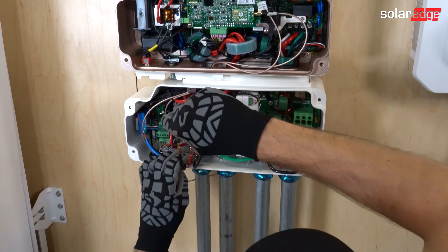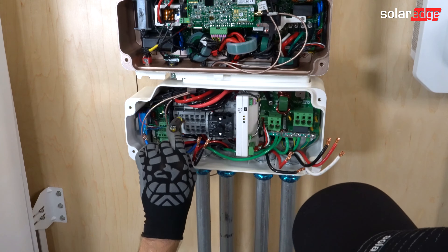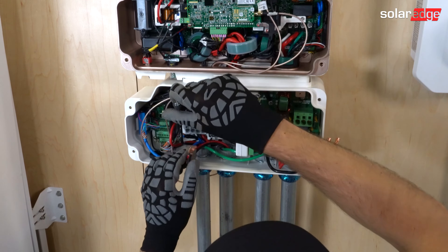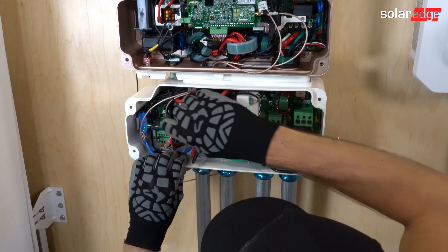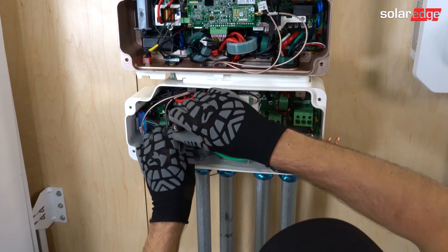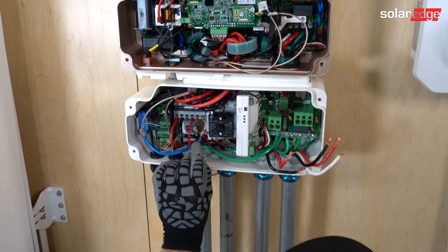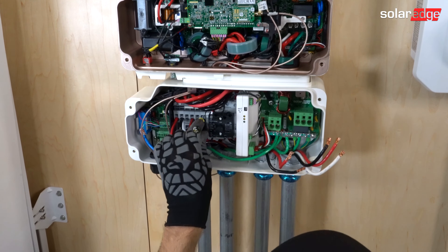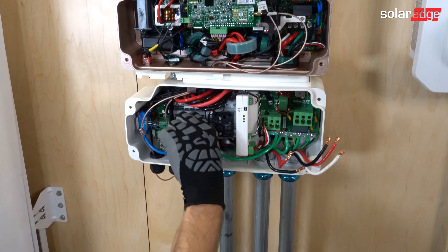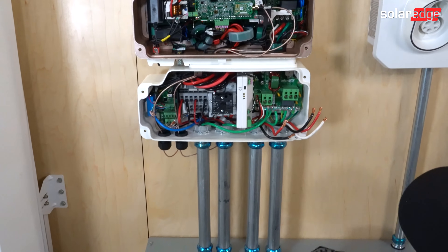So I'm going to move on to our negative, and then to our PV positive, and our PV negative. Make sure before you land your PV positive and minus for each string to test an open circuit voltage to make sure you have the correct amount of optimizers checking in.